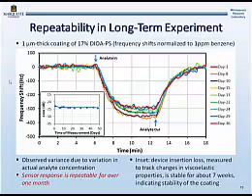So you can see that from day to day, there is no systematic trend in sensitivity. So there is just a random scatter, which is probably due to the variation in the actual analyte concentration. Otherwise, the sensor response in terms of response time and sensitivity is repeatable for over 1 month.